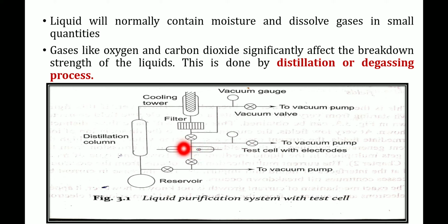Very important: the electrode separation is very critical in measurements with liquids. Also, whichever electrodes we use, either sphere electrodes or uniform parallel plane electrodes, the surface of those electrodes should be very smooth. Getting my point? And for testing the breakdown strength of a particular oil, the test voltage is first very low, of the order of 50 to 100 kilovolt.